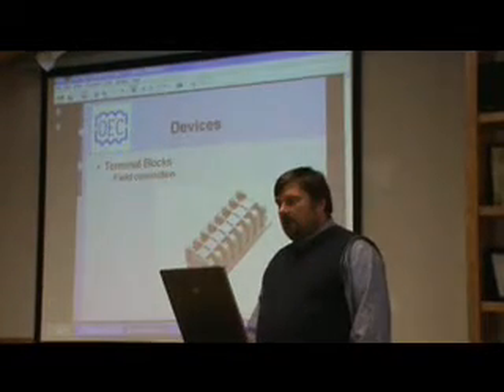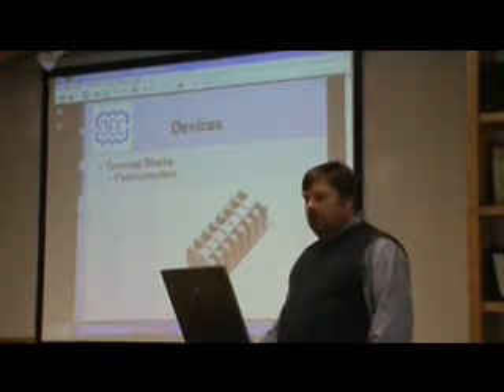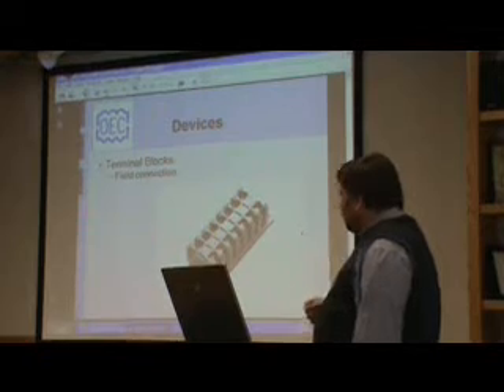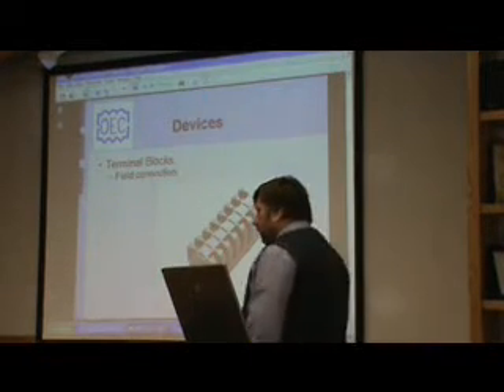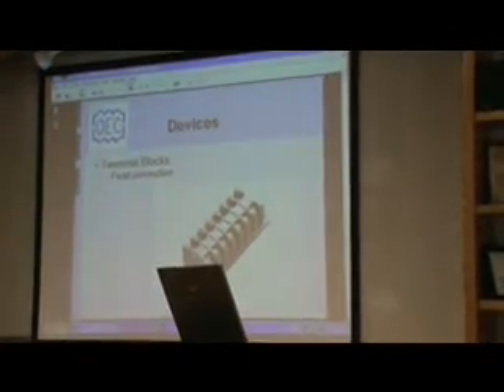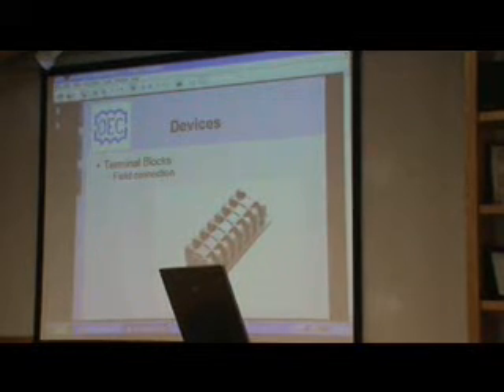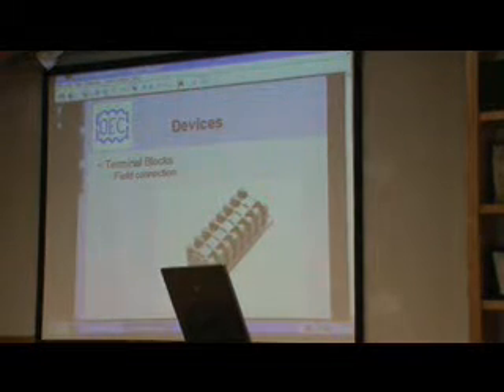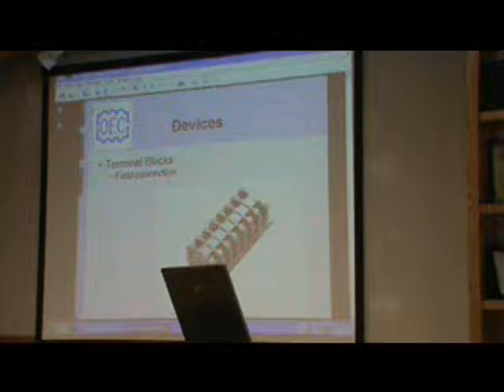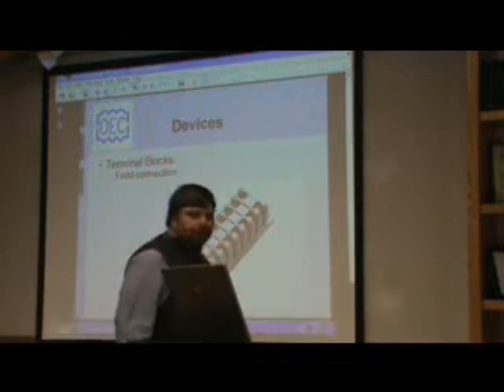The next block you're probably going to see when you're hooking up your float switches or any pilot devices that you have for alarms that are going out of the panel are these field terminal block connections. In all of our panels, we use the Marathon blocks that are a little bit larger. You can actually get a full-size screwdriver blade into those. It's just a little bit nicer feature, so you don't have to have those little screwdrivers to get in and mess with the panels when you're hooking up stuff.